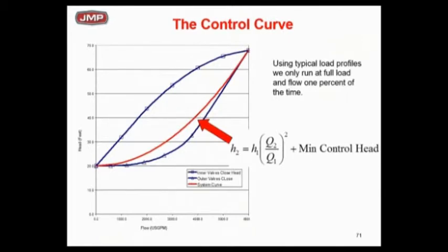Let's assume I need 3,000 GPM. What pump head do I need? Ah, I'm at 3,000 GPM, what pump head do I need? If the two-way valves closest to the pump are open, then I need, what, about 25 feet?